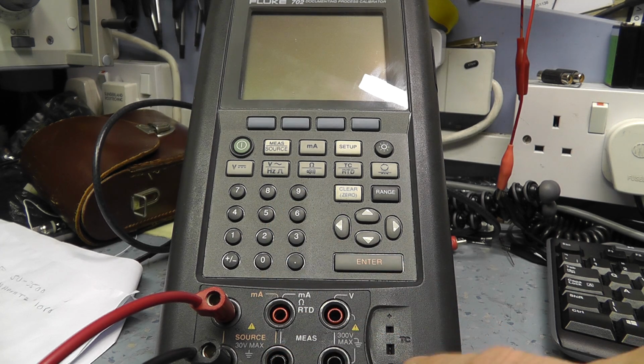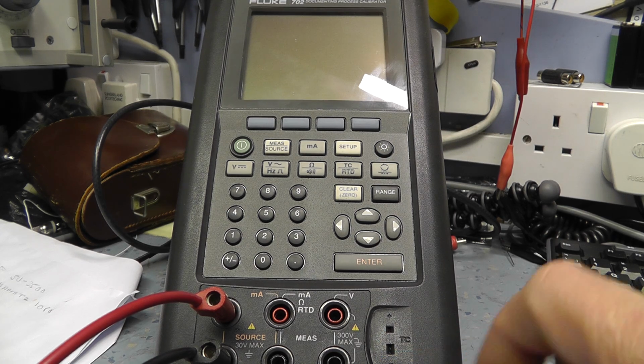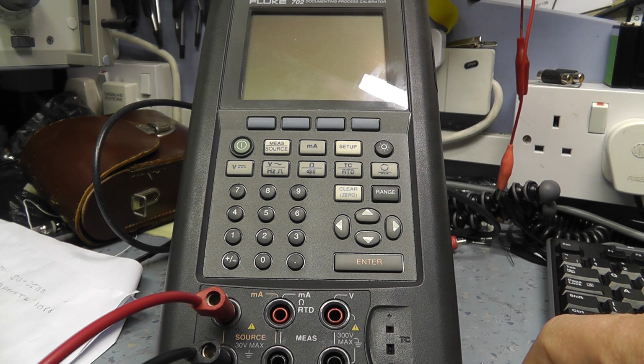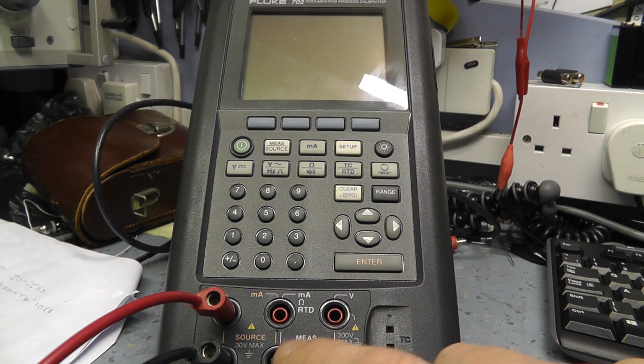The thermocouple input - when you generate a signal, because these types of thermocouples like the K-type work on dissimilar metals, any voltage potential you get between the two is simulated here and fed into your thermometer, and therefore you can check your thermometer for accuracy. So that's in its source mode.